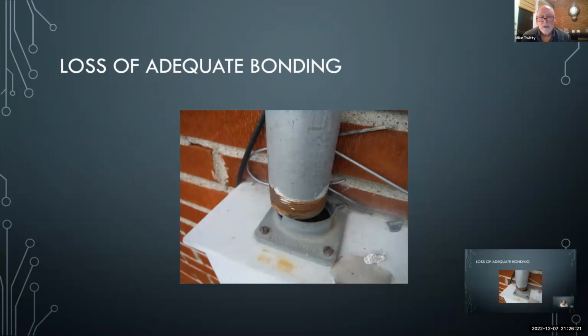This is a metal conduit riser that is broken loose from the threaded hub that goes into the top of this meter base, and that's what bonded that conduit. So it doesn't have a good bond. I mean, that hub is what bonded it to the equipment. So that's a dangerous deal when that pulls loose.